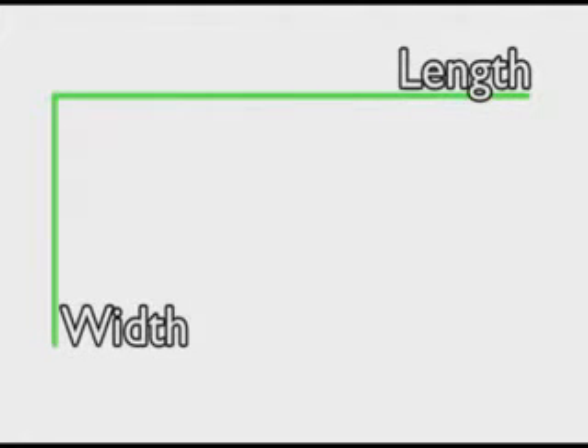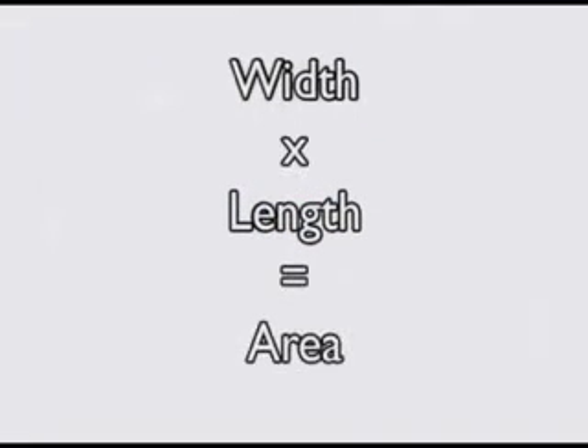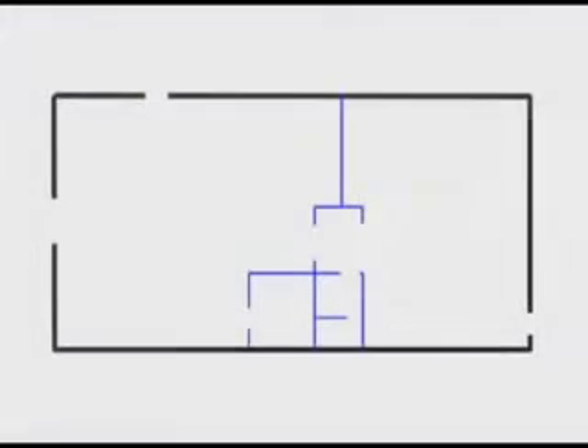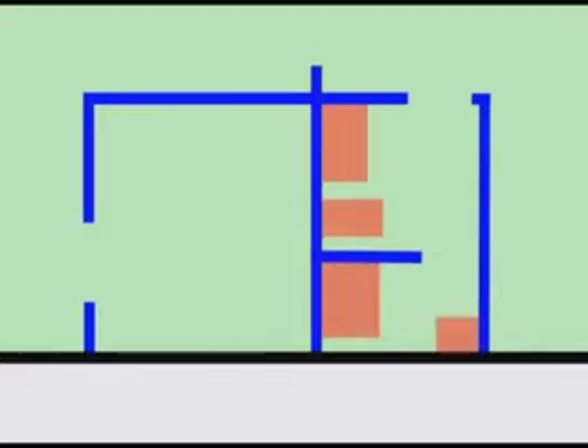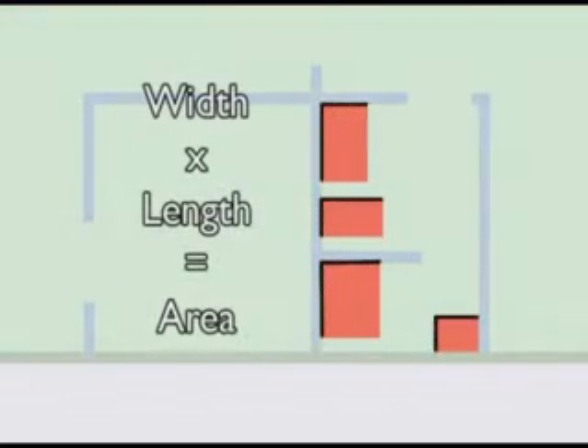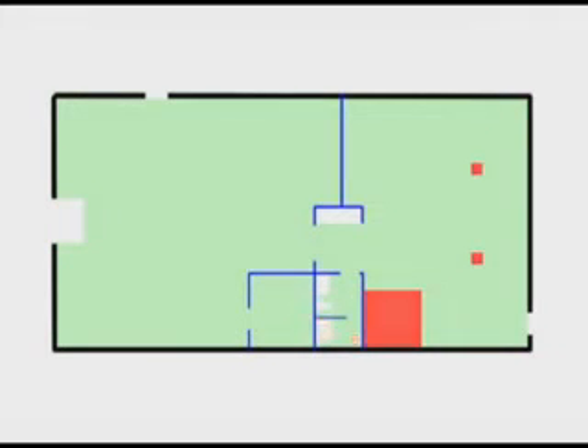You can now proceed as shown in this example. Draw a sketch to scale of the area to be covered on a sheet of squared paper. Using a calculator and a few basic mathematical formulas, determine the areas which are to be heated. First, multiply the length by the width of each room to calculate its total surface. In each case, subtract all the areas which will not be heated from the total area you have just calculated. To do this, multiply the length times the width of all fixed objects in order to calculate the extent of the surface they will cover. Finally, subtract the area of all the objects from a room's total area to determine the net heating area.